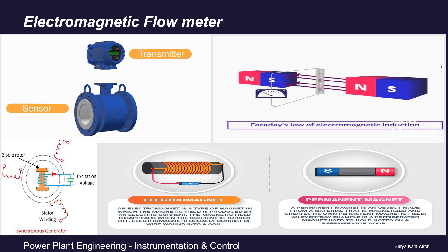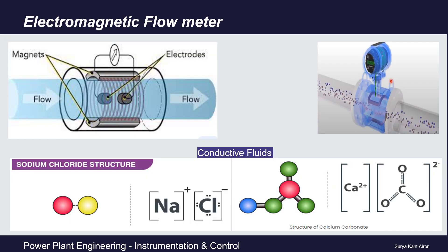In our electromagnetic flow meters, we have electromagnets connected to an electrical power source, which generates a magnetic field in that cross-section between the two electromagnets. To fulfil Faraday's law of electromagnetic induction, we need a conductor moving perpendicular to the magnetic field. In the case of electromagnetic flow meters, the fluid flowing through the pipeline serves as the conductor.